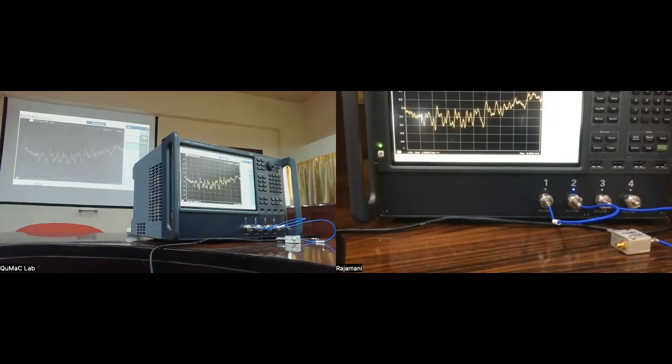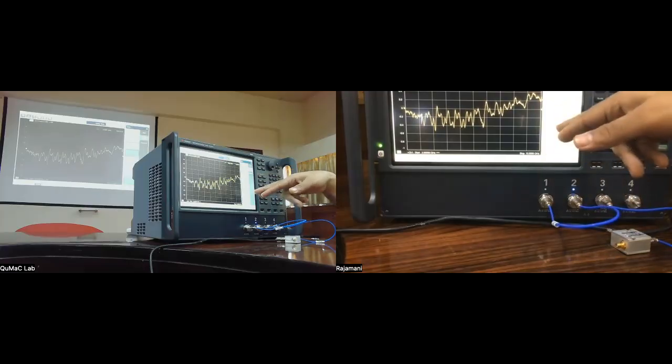So there was a length there, the electrical length. There are other ways you can enter this. The method I have chosen is just visually confirming that this is doing the right job. But if you know your coaxial line and its properties, in terms of its velocity and so on, you can enter them directly here.